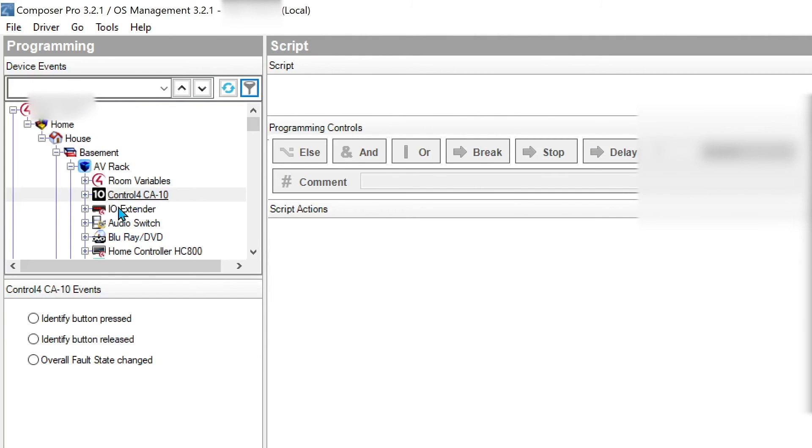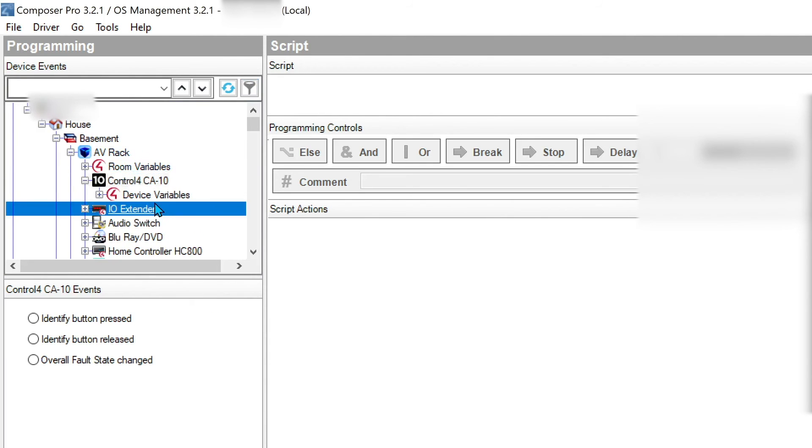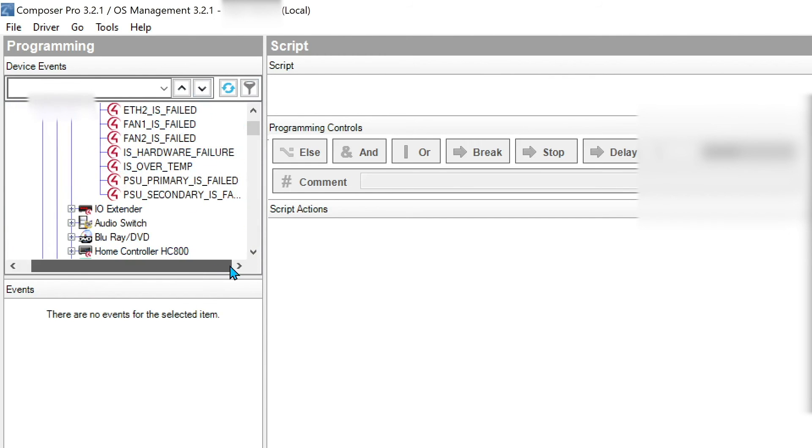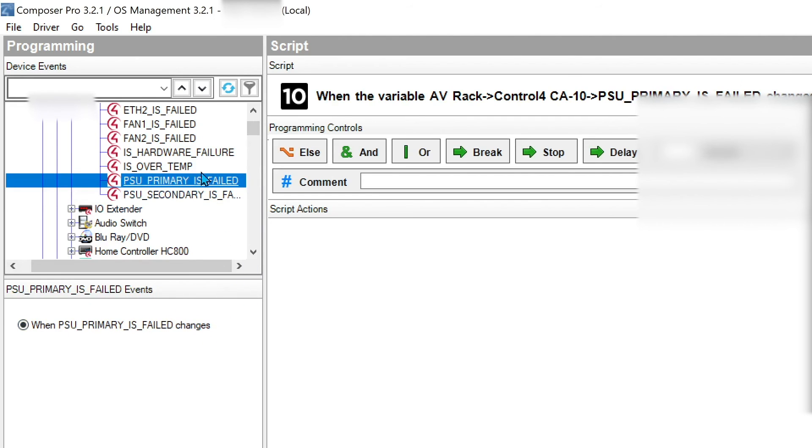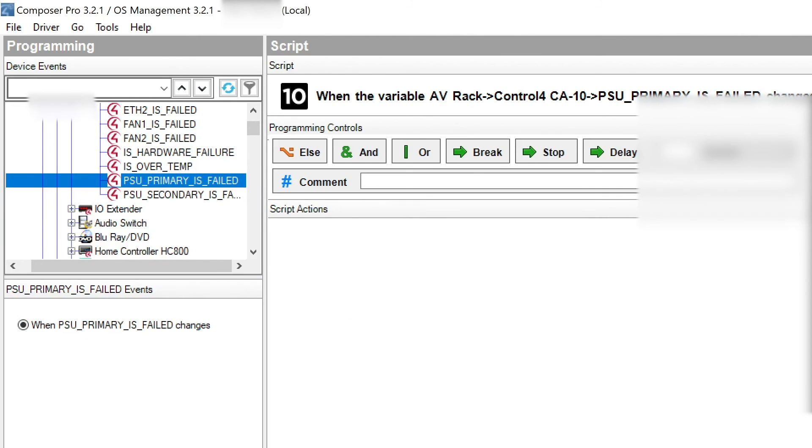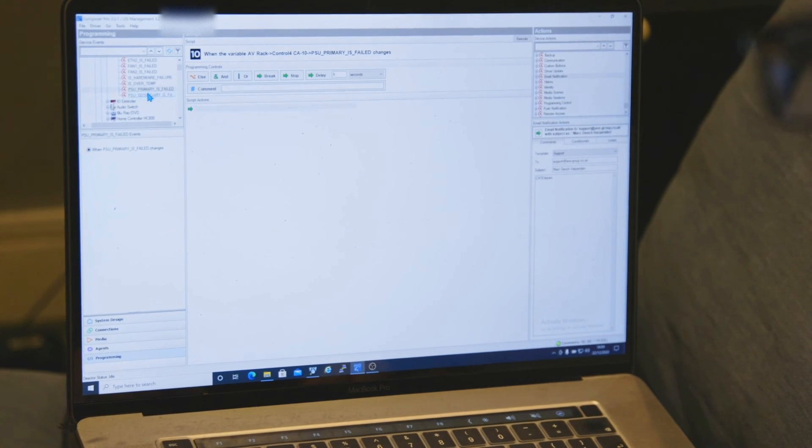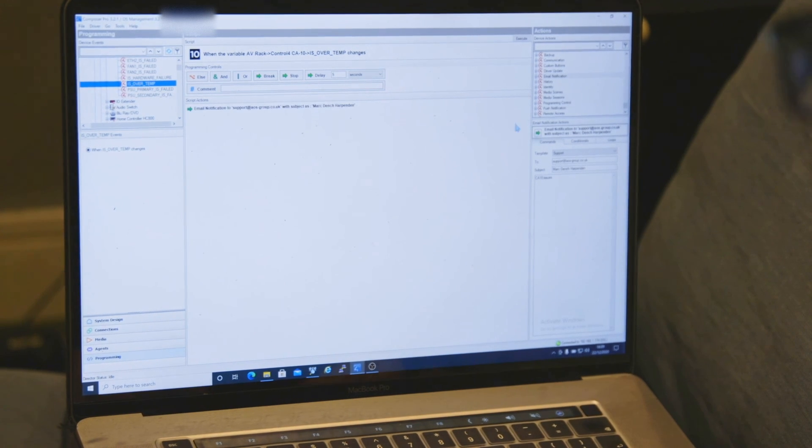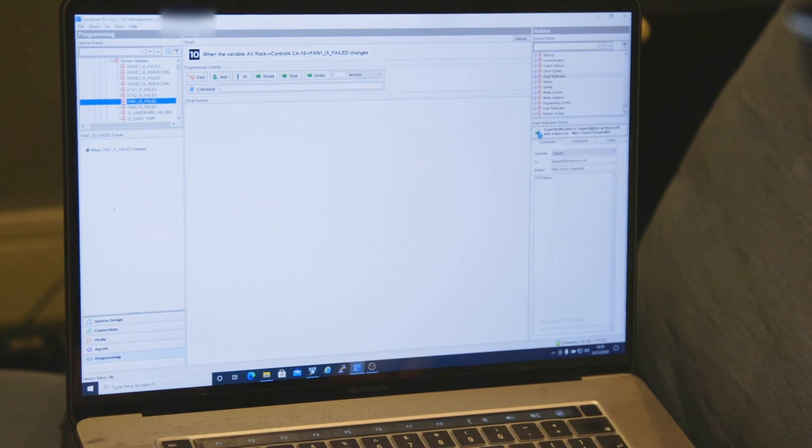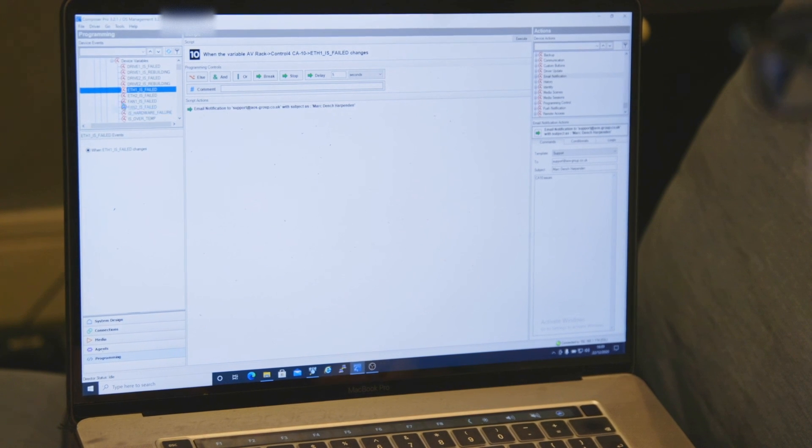One thing that I'm going to show you with the CA10 is, if we come into the device, we have device variables under here. And then we've got everything on here. So we basically have all the fault conditions against the primary and secondary devices. So if I come down into my email notification agent down here, we've got a support email on the project. So I'm just going to come back against every fault condition and add this in. And then basically we don't need to report what the actual fault condition is and create an alert for every single one. Because if we get an alert, we can log remotely into the system and see what's wrong with it. So we tie back all these alerts back against there. And effectively what this is going to do, it's going to email a notification to support at AOS group if there is an issue with this device. And then we know when to contact the client and have a look and see what's going on.